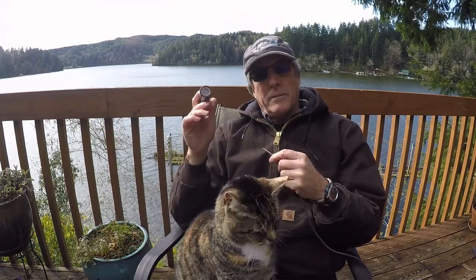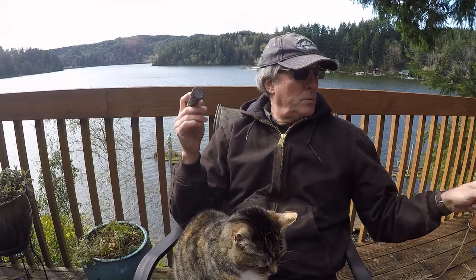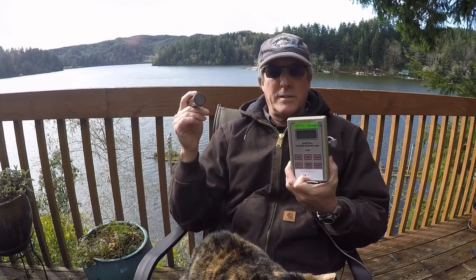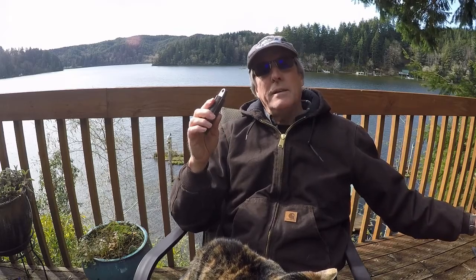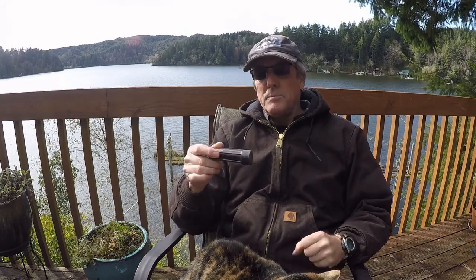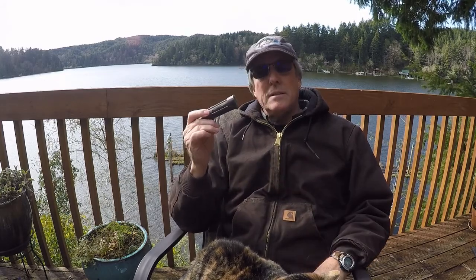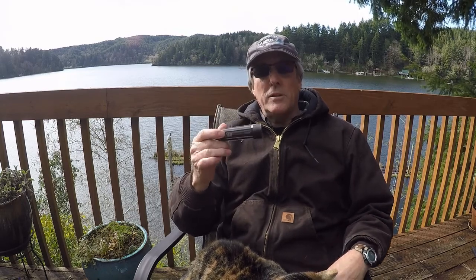We'll then download the data from this and look at it and compare that to the readings that we wrote down from our NIST thermometer. We'll compare the two, and hopefully if we can get them within 0.2 degrees plus or minus, if this is within that range of the NIST thermometer, then we're good to go, and we're confident that this is taking the readings that we want to, and that they're both accurate and precise. So I'll get that set up and get the computer set up, and I'll be back to show you that.